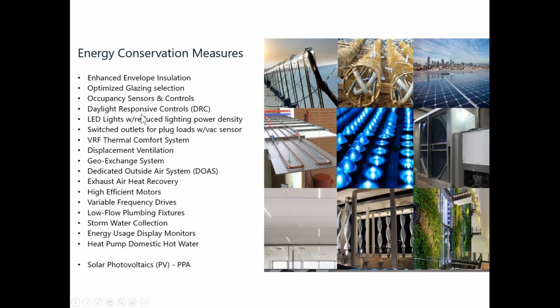We have daylight responsive controls throughout the building. We have LED lighting everywhere, including the gym and the auditorium. We have switched outlets for the plugs with a vacancy sensor in the learning centers, really in the classrooms. What this is doing is turning off our phantom loads when the teachers are not there. So every room does have a smart display in there, and the smart display will turn off after you leave the room based on the vacancy timer sensor.